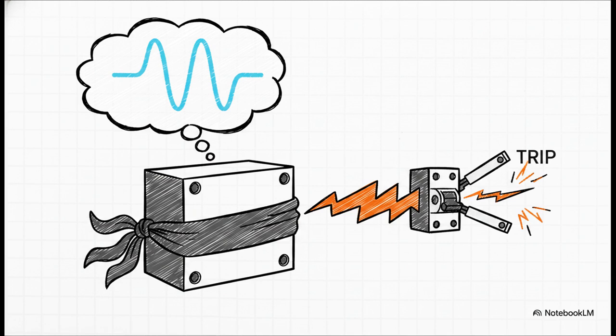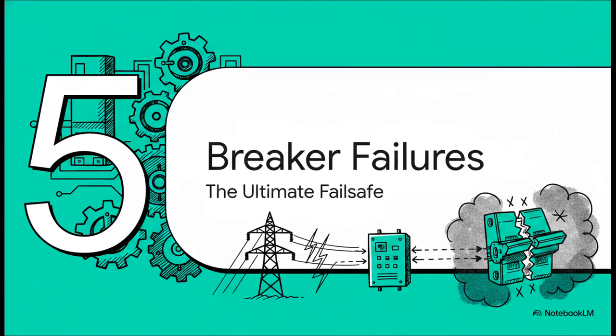To solve this, modern relays use switch-on to fault, or SOTF, logic. It utilizes a clever memory feature of what the voltage was just before the line was de-energized. This allows it to instantly recognize the dead short and trip the circuit before disaster strikes. Section 5. Backups and breaker failures.